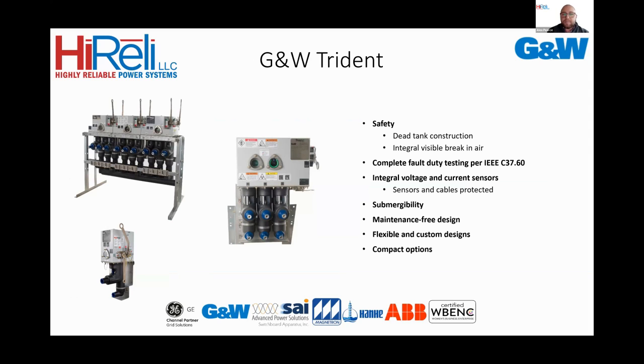G&W Tridents: dead tank construction, integral visible break in air, no oil there. Complete fault duty testing per C37.60. All the voltage sensing and current sensing is molded within the modules. There are no external elbow voltage sensors, no external CTs unless you have a ratio that you want. This reduces the footprint. You don't have to worry about rats or anything down there chewing on the cables. Fully submersible, tested under 20 feet of water for 20 days. Maintenance-free design, and then we have flexible custom designs and compact options.